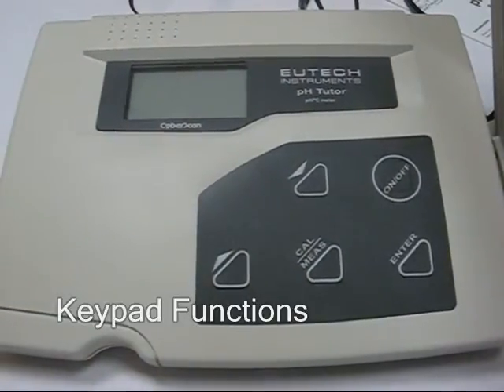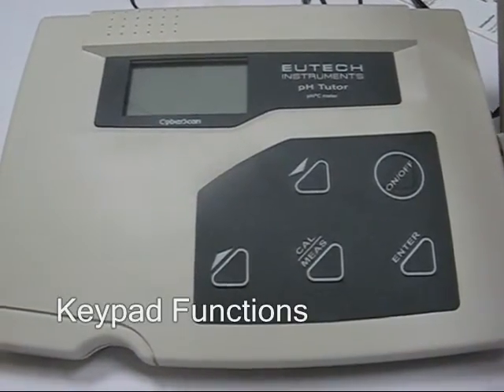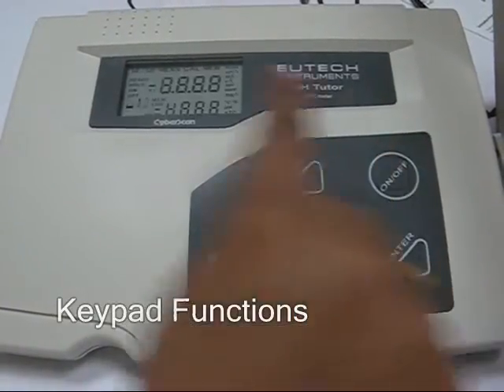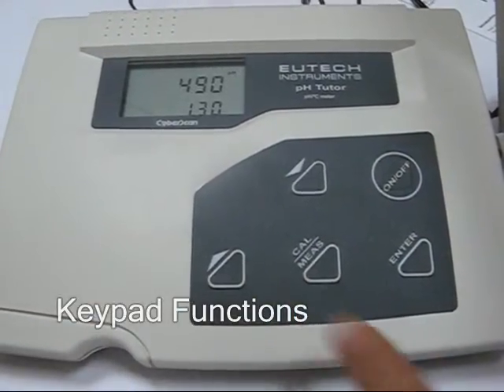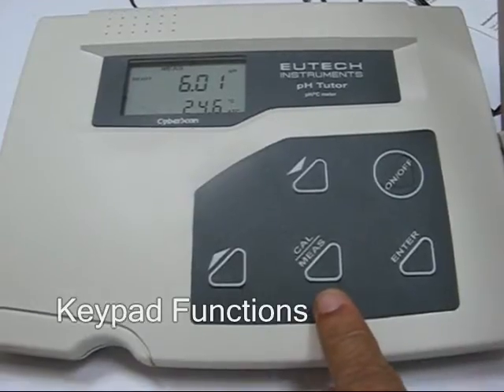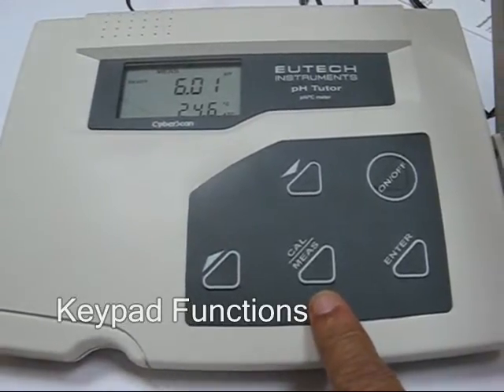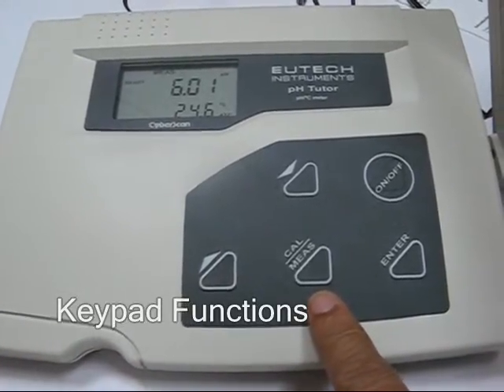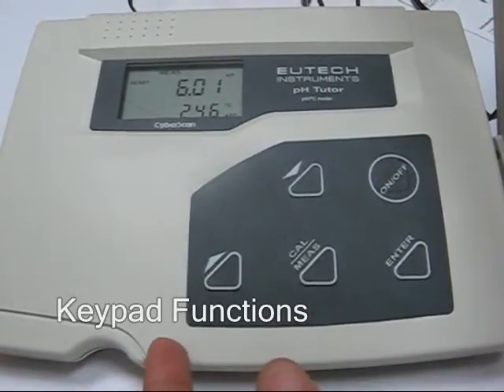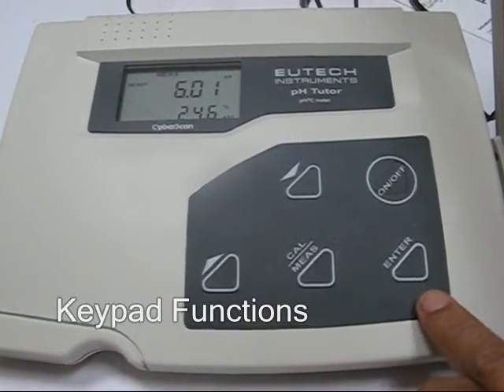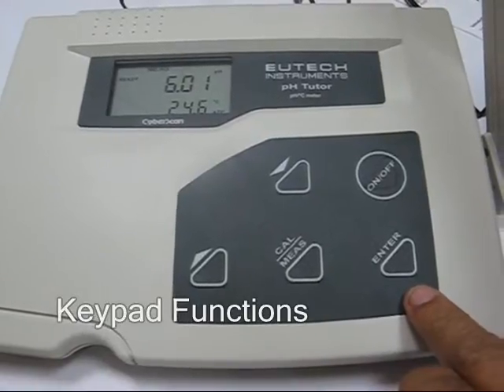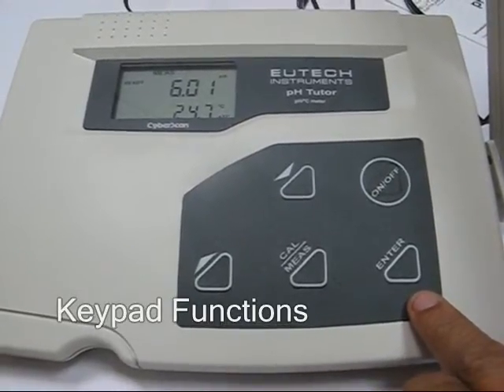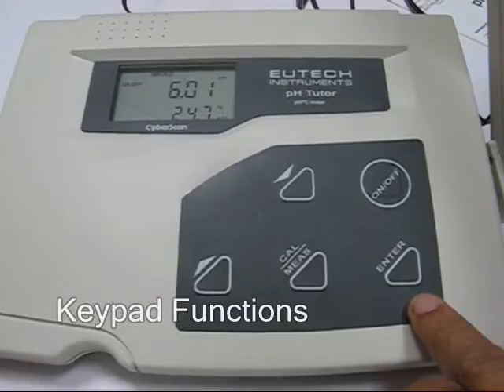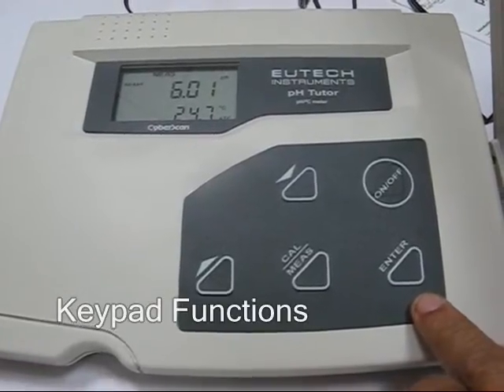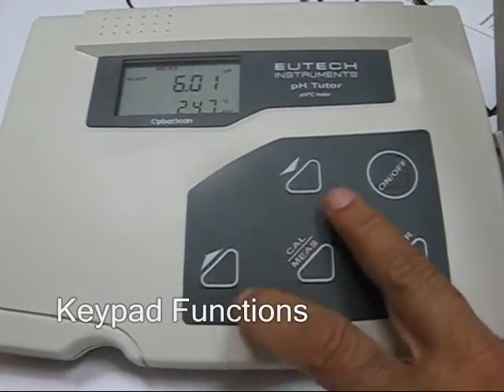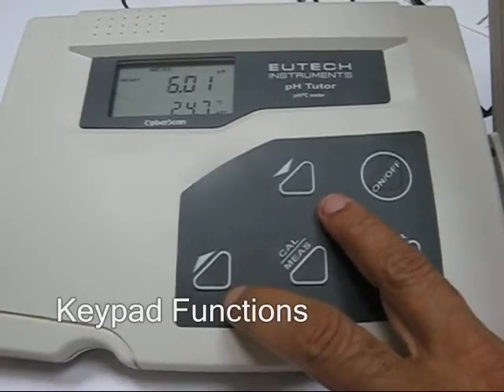We will now look at the keypad functions. On-off key turns the unit on or off. Cal measure key helps toggle between the calibration and the measurement mode. If you are in the calibration mode, hitting the measurement key will bring you back to the measurement mode. The enter key helps confirming a selection if you are in the setup menu, or if you are in the calibration menu, you can confirm the calibration by pressing the enter key. That leaves us with two more keys, which is the increment and decrement keys.